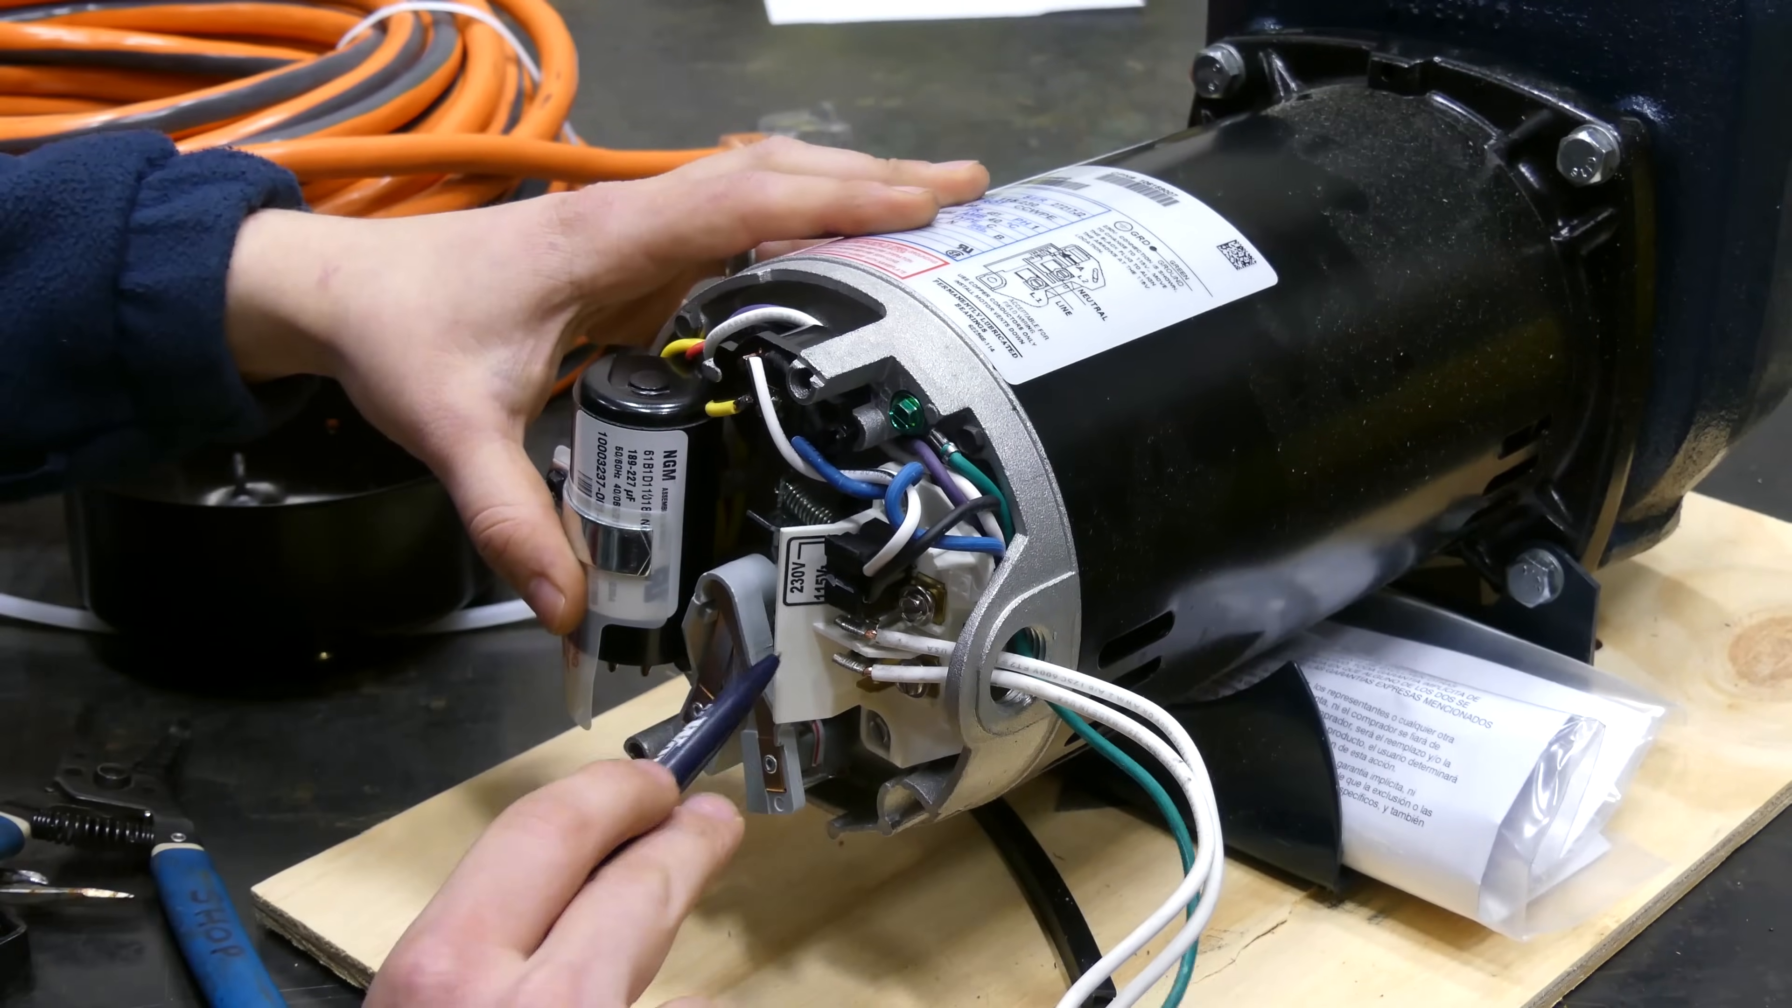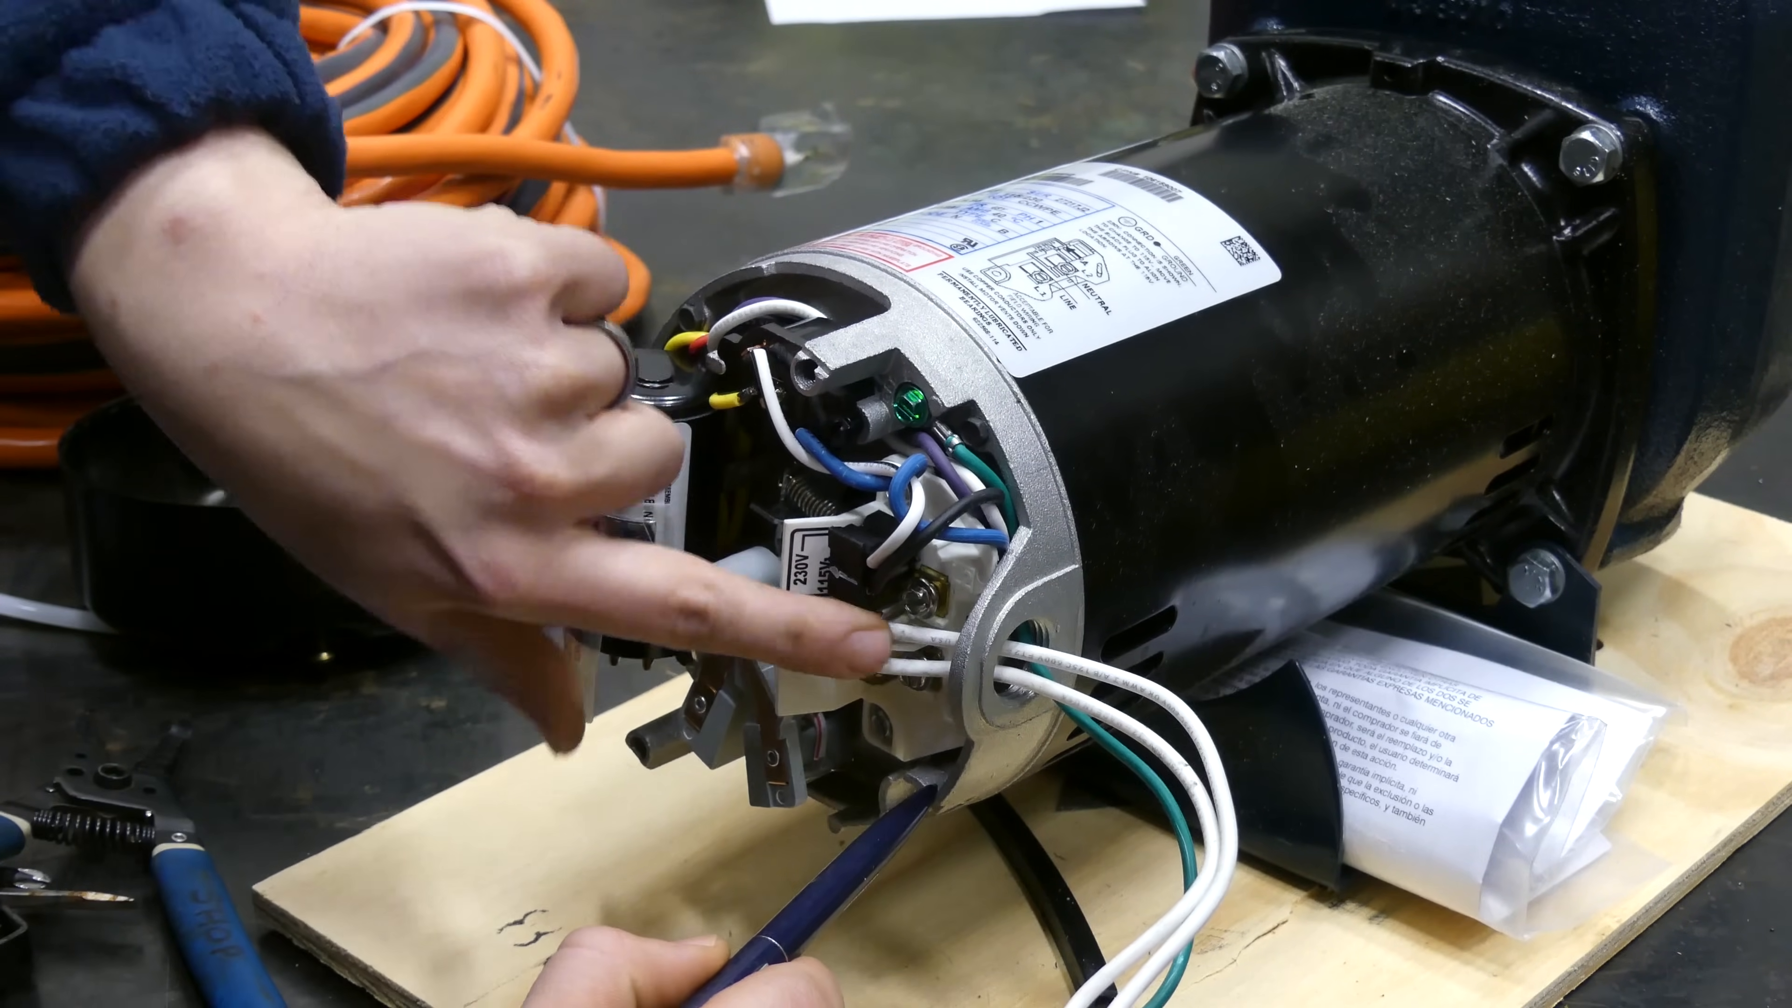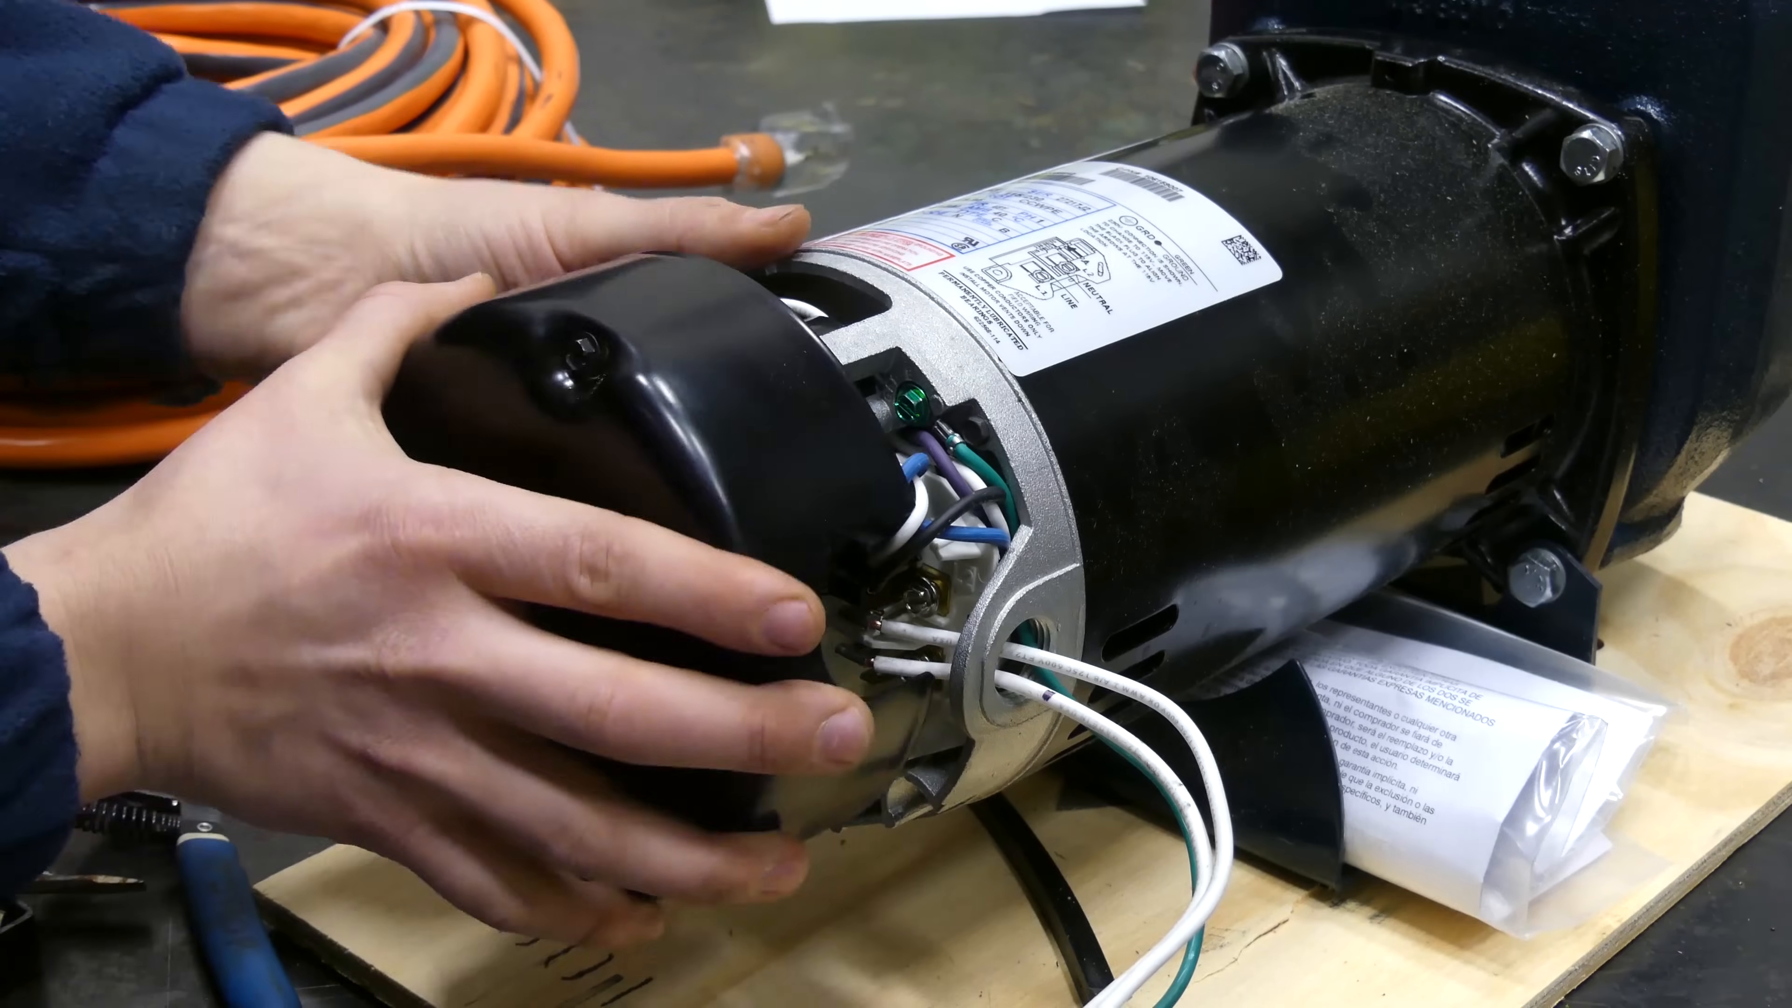Before I throw the back plate on, I do want to just point out one thing here. You want to pay attention, and it's on the motor here, but you want to pay attention to your neutral in 120 volt and your hot leg. There's a diagram on top of the motor that says that L2, which is the top one here, is our neutral, and then L1 is our line one. So I'm just going to mark line one with some black, so I know once I got the back plate on which wire goes where. So now we'll throw this back plate back on here.